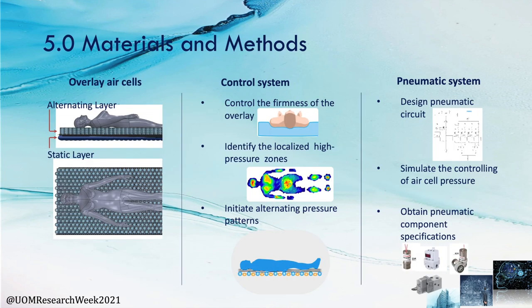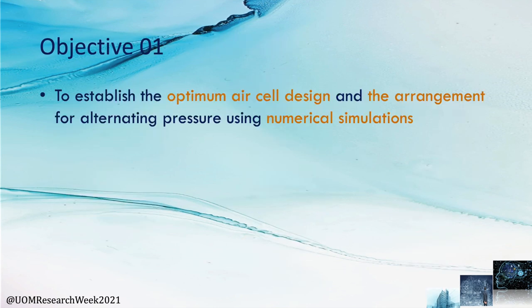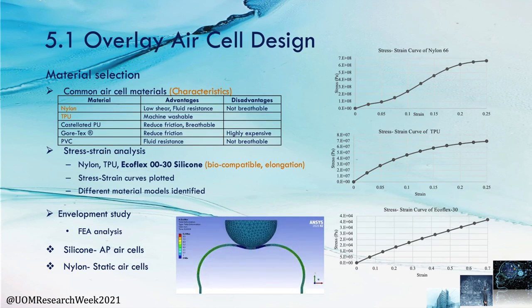The design is categorized into three parts: overlay air cell design, control system, and pneumatic system. The overlay air cell design has two air cell layers to avoid bottoming out, which is the collapsing of air cells onto the bed frame. The control system creates pressure feedback and controls the internal air pressures. Material selection considered common materials used in existing mattresses; silicone was also studied due to its biocompatibility and elongation. Silicone was selected as the top air cell layer for formulating alternating pressure therapy, and nylon was used to fabricate the bottom air cell layer to avoid bottoming out.